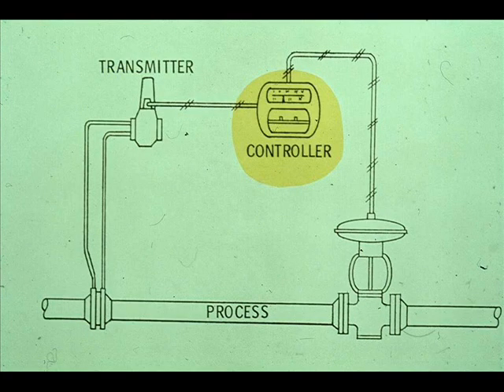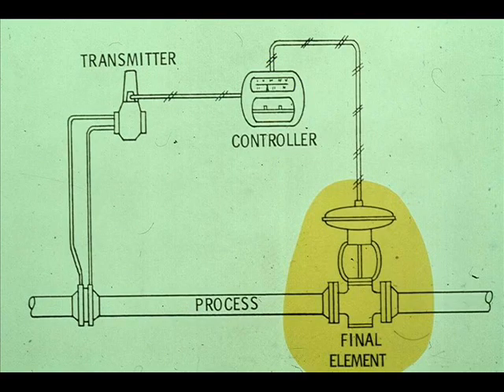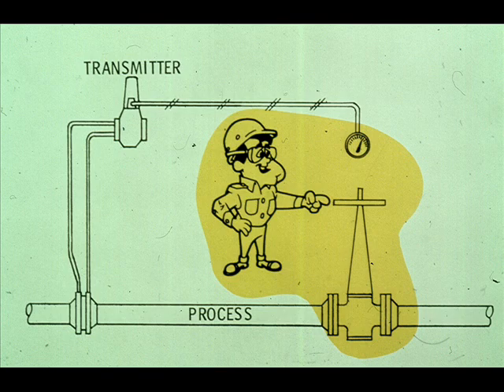The controller compares the transmitted signal with the set point, and then signals the control valve to open or close as necessary to hold the flow at the set point. The control valve, or final element, receives the signal from the controller and takes whatever action that the controller indicates is necessary. All of the control loops that we have examined are closed loops that provide continuous automatic control. If we remove any part of the closed control loop, it then becomes an open loop. This is an example of an open loop. A person has replaced the automatic controller. This operator reads the indicated flow on a meter, and then manually adjusts a hand control valve as needed to obtain the desired flow rate.